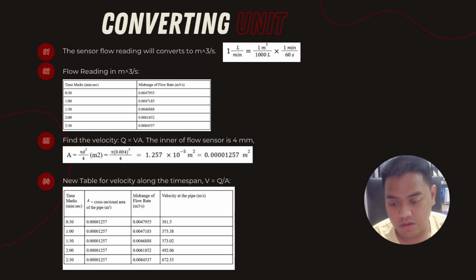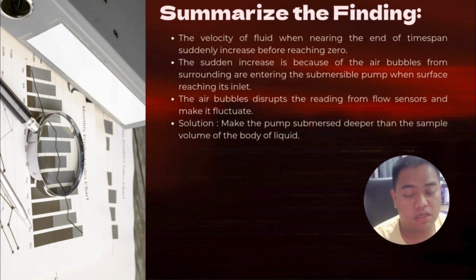So we shall be finding our velocity within the time span of 30 seconds, 1 minute, 1 minute and a half, 2 minutes, and 2 minutes and a half. So we find the velocity along the time span will be 381.5, 375.38, 373.02, 492.06, 672.53. As we can consider this an anomaly here, we summarize that the finding of our anomaly near the ending of our operation is that the velocity of the fluid suddenly increases because an air bubble is entering the submersible pump.